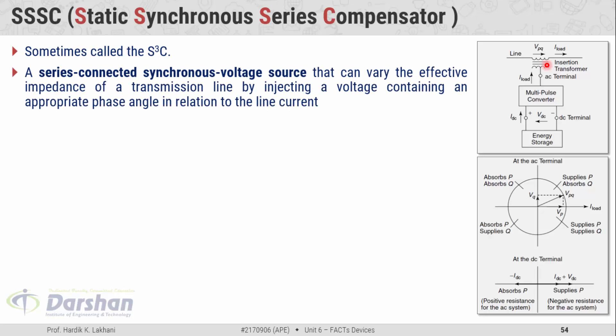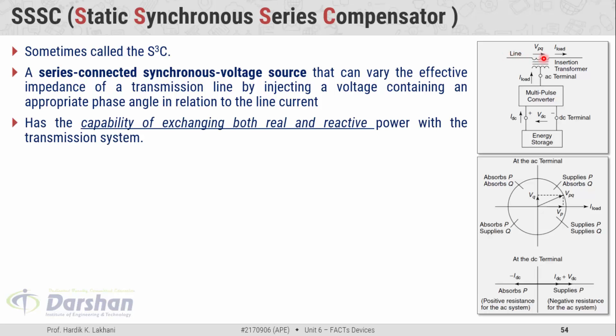SSSC is a series connected synchronous voltage source that can vary the effective impedance of a transmission line by injecting a voltage containing an appropriate phase angle in relation to the line current. This is the working principle of SSSC. It injects a voltage of proper magnitude and with a specific phase angle with respect to the line current. It has the capability of exchanging real and reactive power with the transmission system — same as the STATCOM, it can exchange both real power and reactive power.